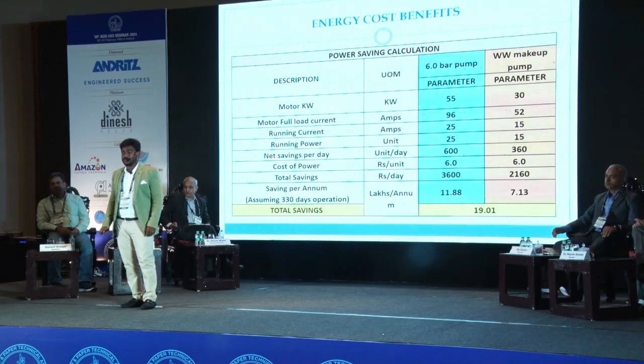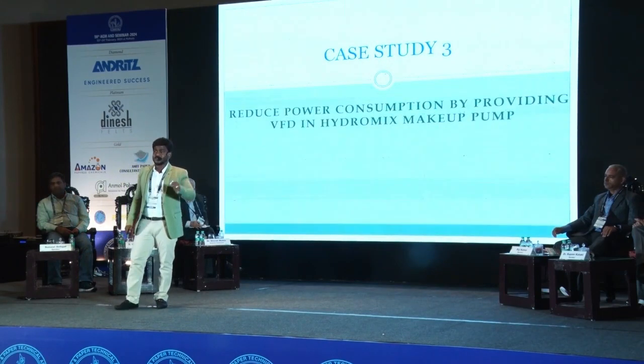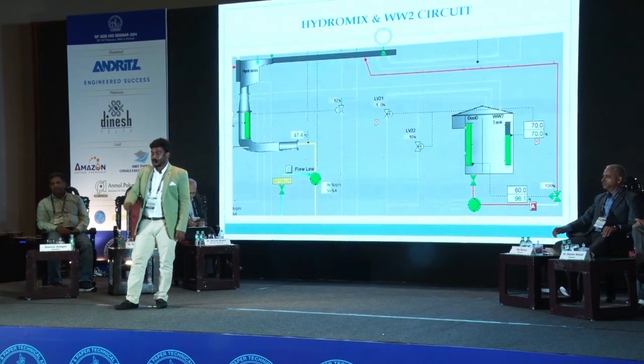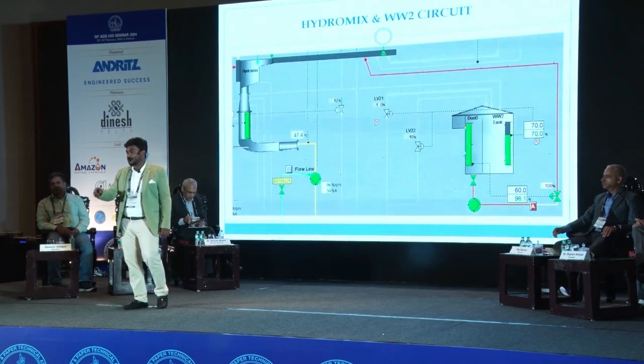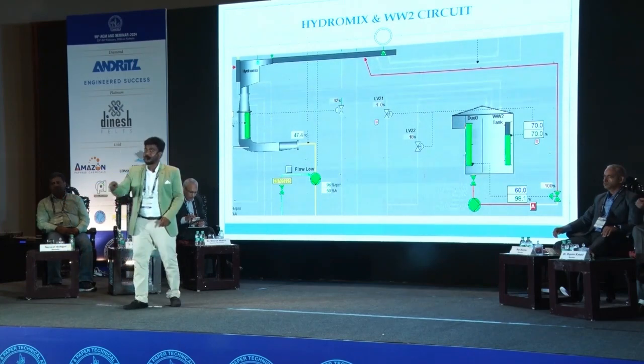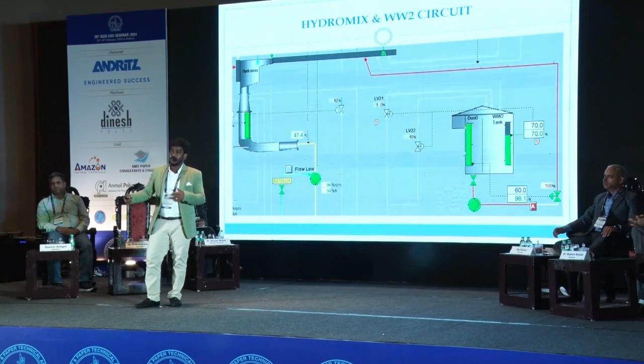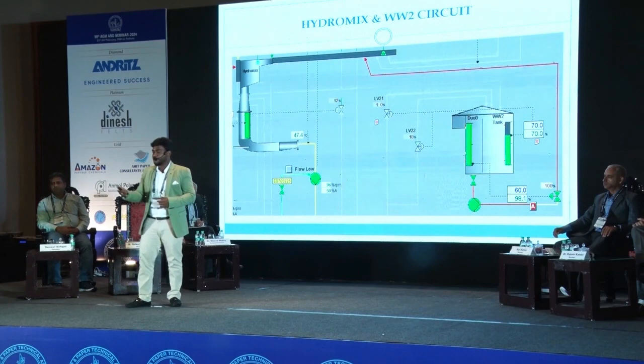And our next case study is reducing power consumption by providing a VFD in the hydromix makeup pump. This is again the pictorial representation of the DCS diagram. We are talking about this DOD pump. The purpose of this pump is to pump the excess water from the DOD to the hydromix, to the silo, to maintain the level as per the process requirement.